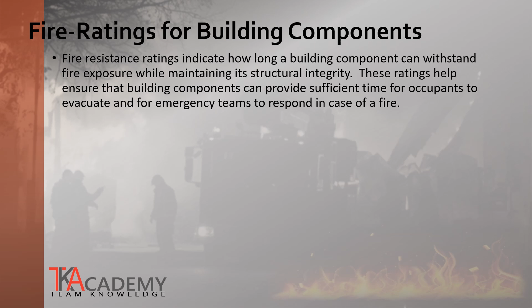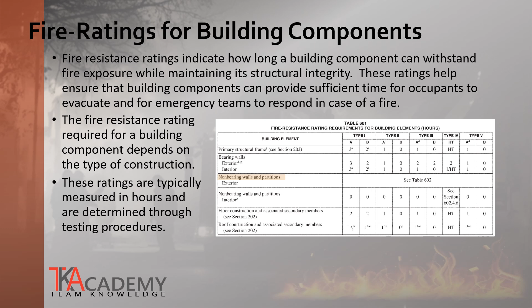The various categories within building components are the primary structural frame, bearing walls for both exterior and interior, non-load bearing walls and partitions at the exterior and interior, floor construction, and roof construction. There are exceptions to the given fire resistance ratings required for the listed components, primarily for the roofs. Fire resistance ratings of primary structural frames and bearing walls are permitted to be reduced by 1 hour when they are supporting a roof only and are not supporting other floor levels.